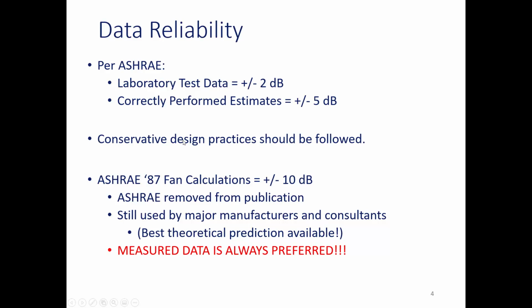So conservative design practices should be followed. This means if you have a really critical job, like a concert hall, you're going to want to design so that for the worst case scenario - that very worst day of the year when they need the most cooling - it's going to be 5 decibels below the criteria. So even if you performed everything correctly, you still might get plus 5 decibels of what you predicted. If you do that, that would be a conservative approach, and it would make sure you would always meet the criteria.